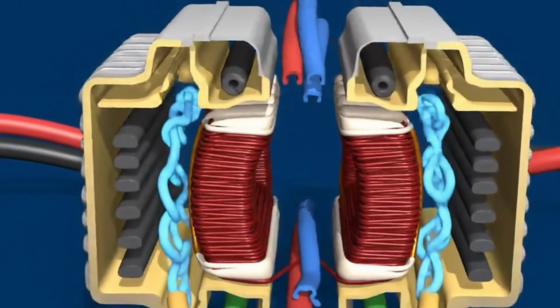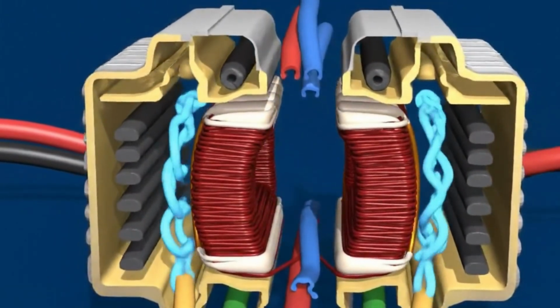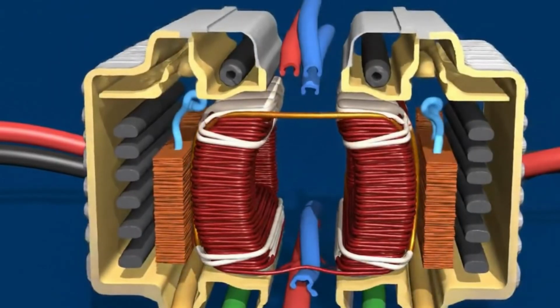Once the electricity reaches an area close to where it's going to be used, we step the voltage down again using step-down transformers, and this happens in stages. From 220,000 volts to 66,000, to 11,000, and finally down to 400 or 220 volts, which is what we use in our homes and offices.